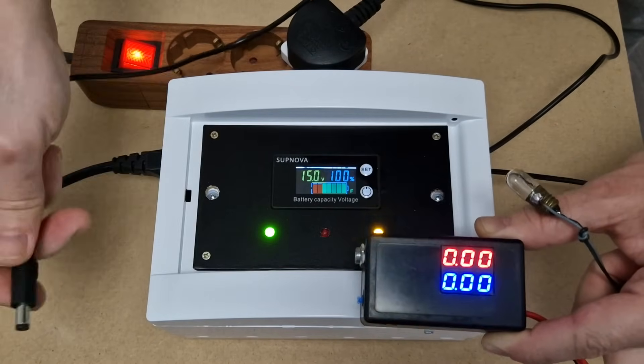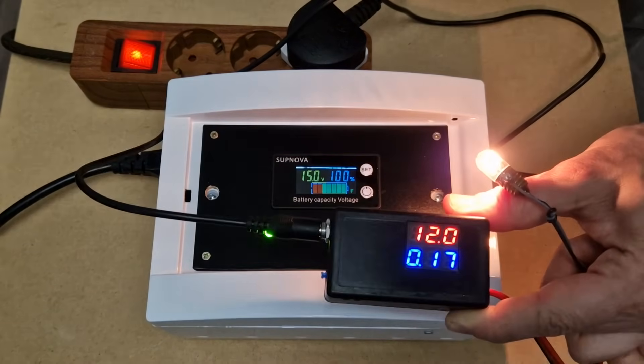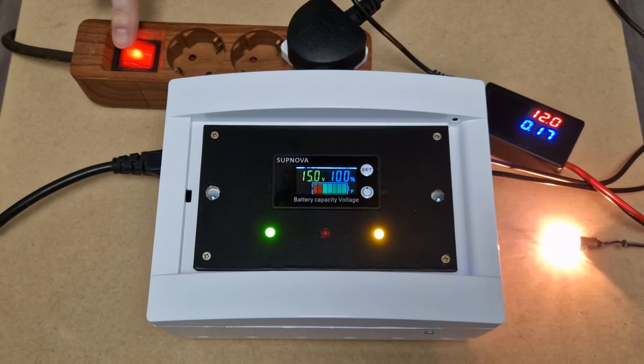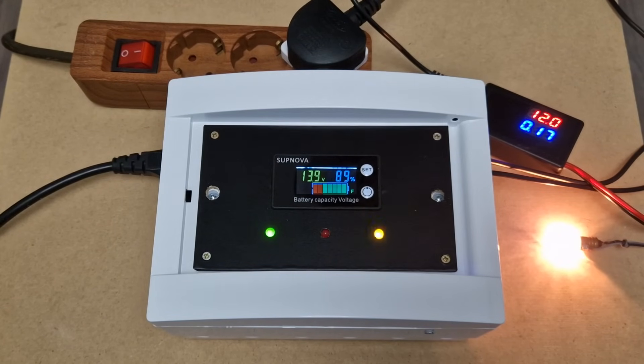Let's check the UPS outputs using a simple light bulb. At the moment, the UPS is running on mains power. This is the 12 volts output. The bulb is fully lit. Let's simulate a power outage. There is no flicker on the light bulb because there is no switching time. All LEDs go out, only the battery indicator remains on. The UPS is running on battery backup.